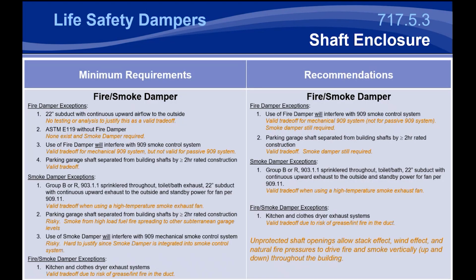Shaft enclosures are actually the easiest way for fire and smoke to spread through a building because fire and smoke has a natural tendency to travel upwards throughout the building. And smoke can actually be pumped downwards if fans don't shut off in the event of a fire and you're dealing with a supply shaft. So these are going to have the most significant amount of requirements, but shafts have also been in the code for quite some time. So there are also a significant amount of exceptions that have been grandfathered into these shafts.